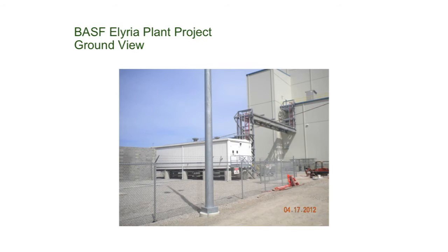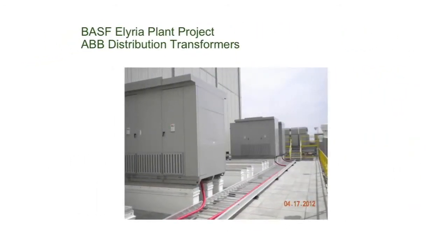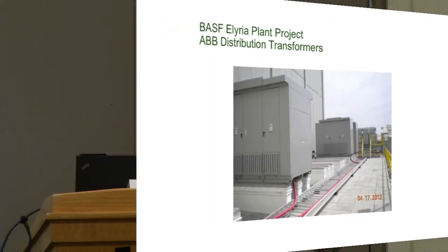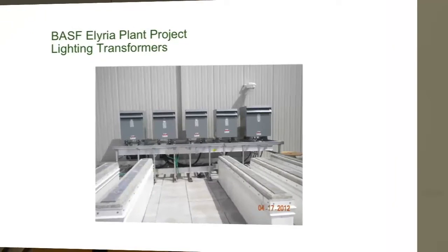Up on the third floor roof are our secondary transformers that came out of Bland, Virginia. And these are the secondaries. The far two transformers are 2 MVA, and the near transformer is 1 MVA. The facility needs 2 MVA, so those are 100% redundant transformers. And the near transformer, the 1 MVA, is only for the kiln power. That only supplies power to the kiln. So the three other bases are for the future kilns at the site.